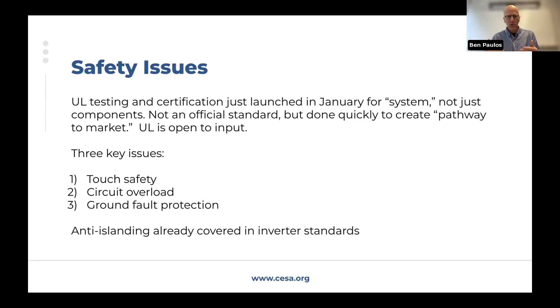The analysis really touches on three issues: touch safety, circuit overload, and ground fault protection. The first question that always comes up is, will this shock someone if the power goes out, with a line worker working on the line? That's already covered in inverter standards from UL. They're already built to do what's called anti-islanding, they shut down the system if the power goes out. So that's not really an issue. But touch safety, circuit overload, and ground fault protection, I'm going to walk through those.